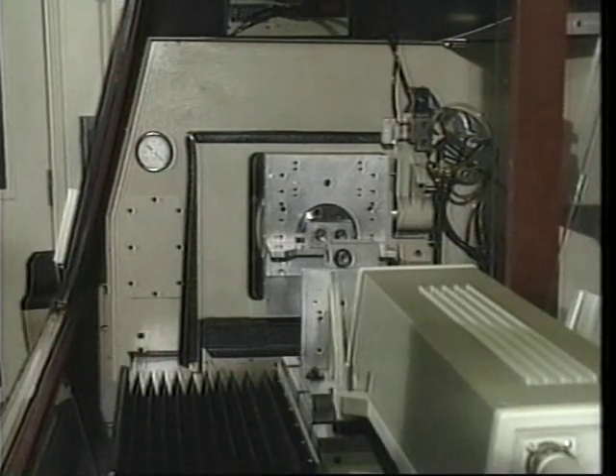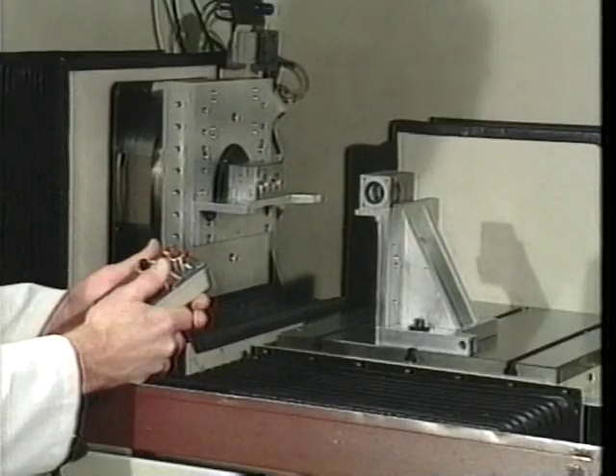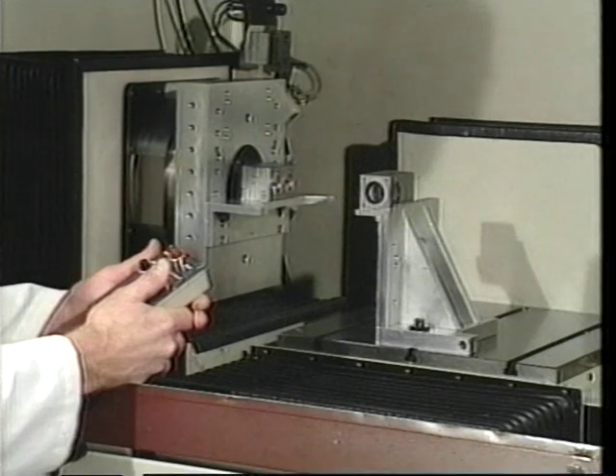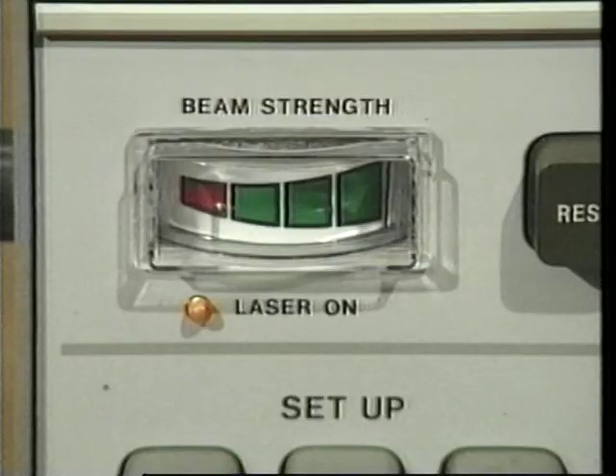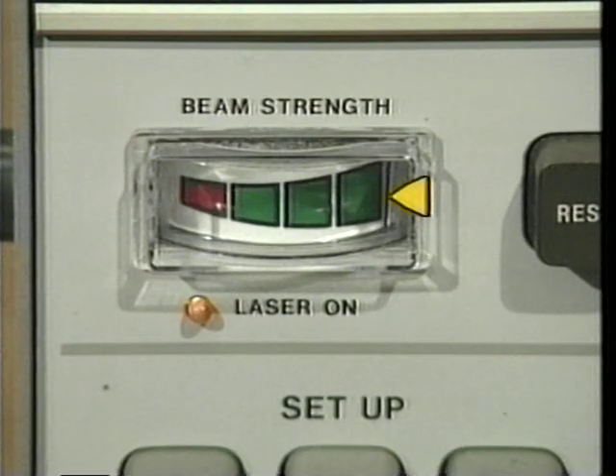is complete. As the z-axis carriage is jogged back to the point of minimum separation of the optics, that is z=0, the strength of the beam being received at the laser head's return port is monitored. The needle on the beam strength indicator must stay in the green area during the full range of z-axis travel. In the event that the needle does move out of the green zone, the alignment of the laser beam with the axis of motion is not satisfactory, and the alignment process must be repeated.